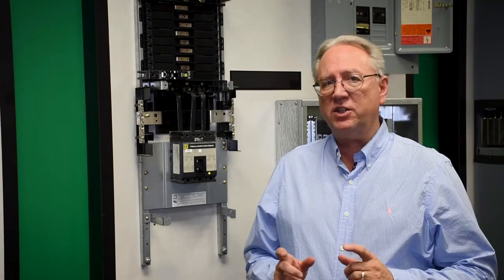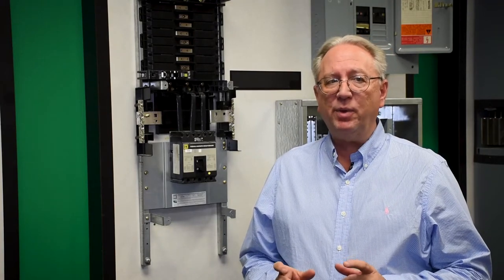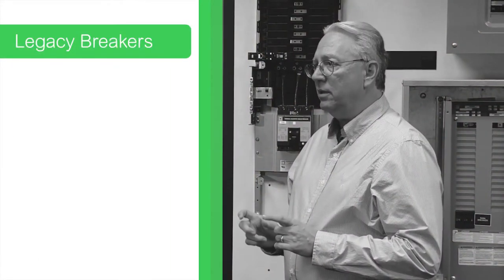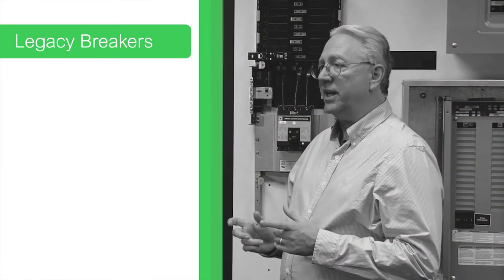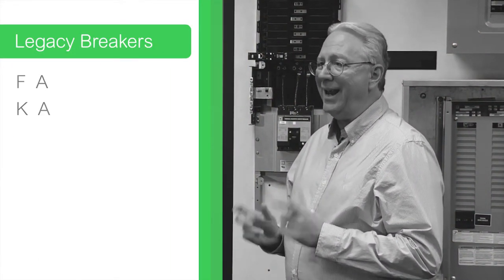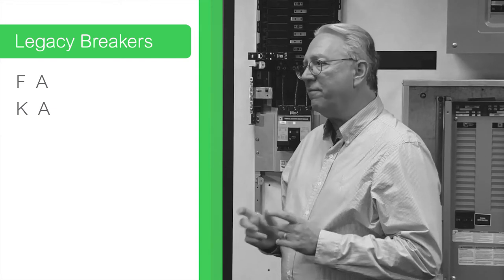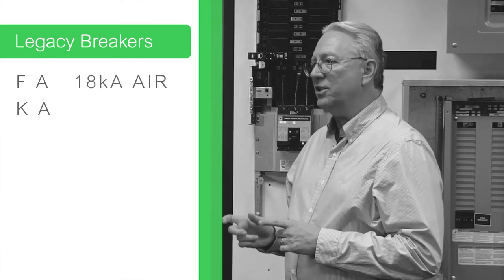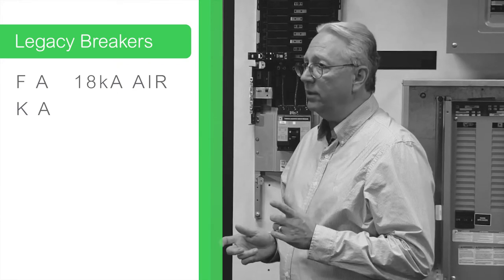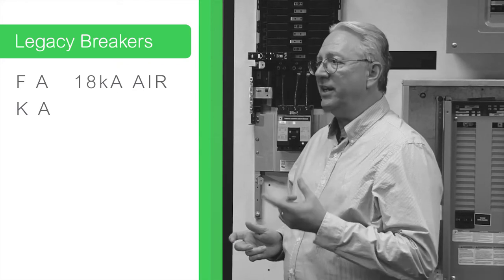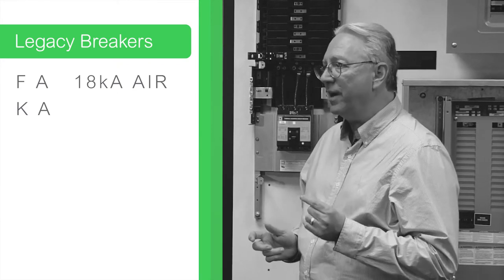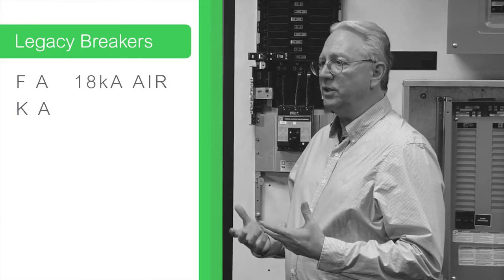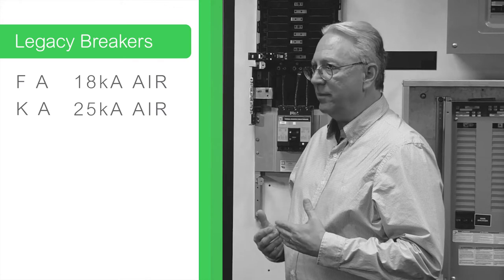The second character is tied to the ampere interrupting rating. On the legacy breakers, if that second character was an A on an F-frame breaker, that meant the breaker could withstand 18,000 amps of fault current. However, if the second character was an A on a K-frame legacy breaker, the fault current it could withstand was 25,000 amps.